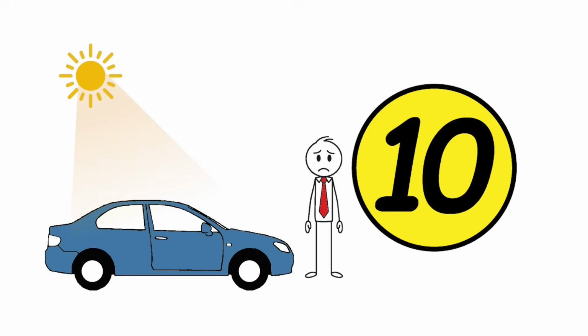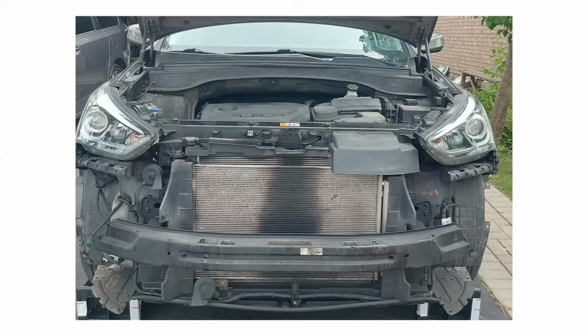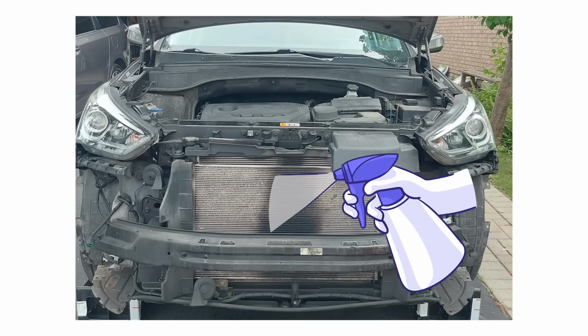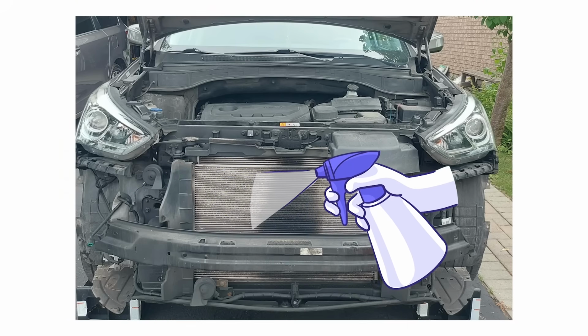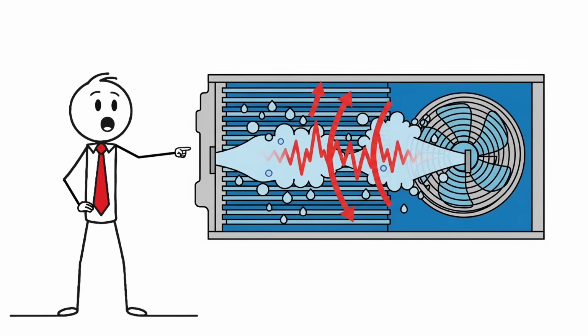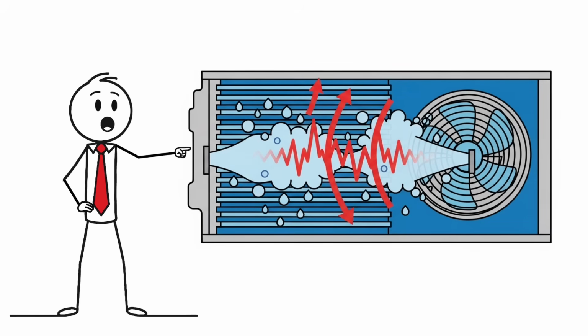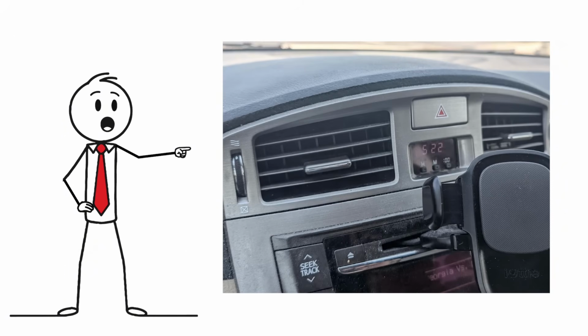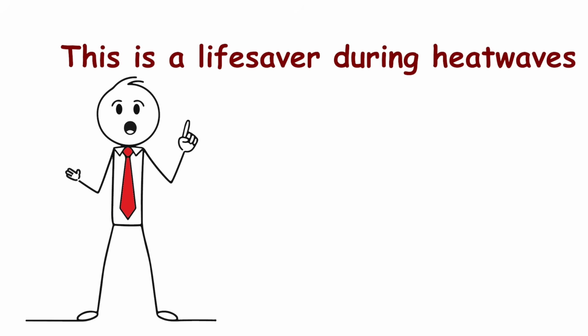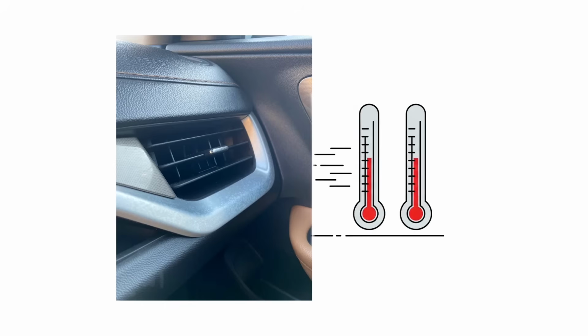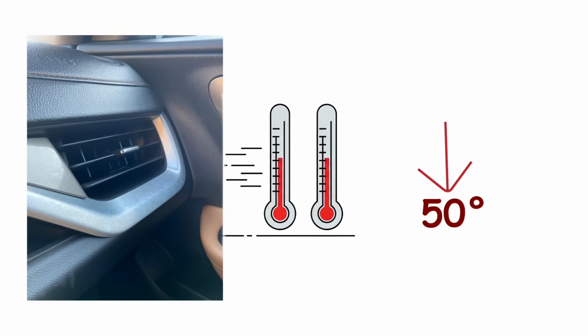Trick number 10 gives you instant, though temporary, relief on the hottest days. Condenser misting. When you spray a fine mist of water onto your condenser through the grill while the AC is running, the evaporation pulls heat away fast, letting your AC work more efficiently. This is a lifesaver during heat waves. Vent temperatures can drop from 70 to 50 degrees in just a few minutes.